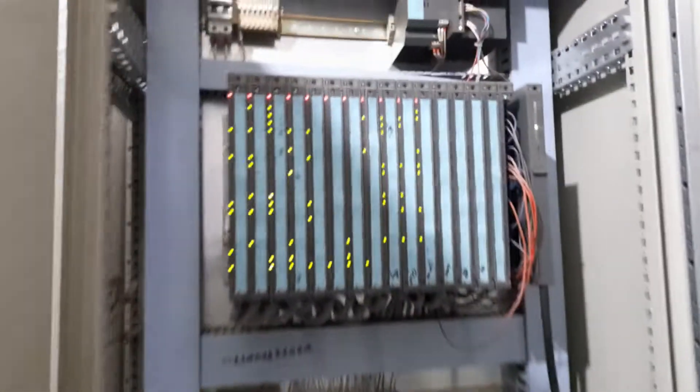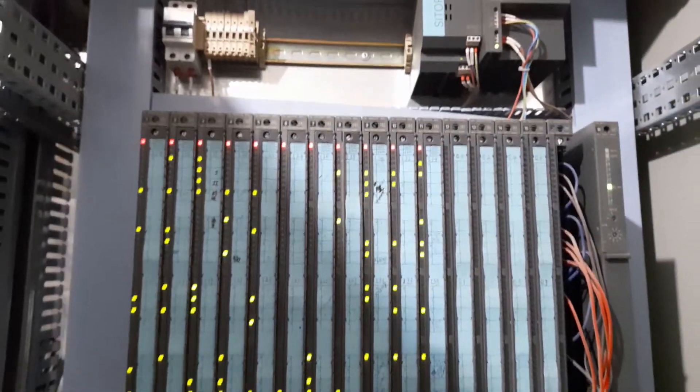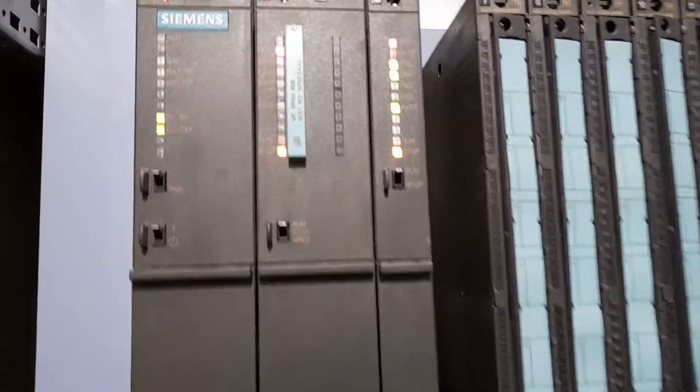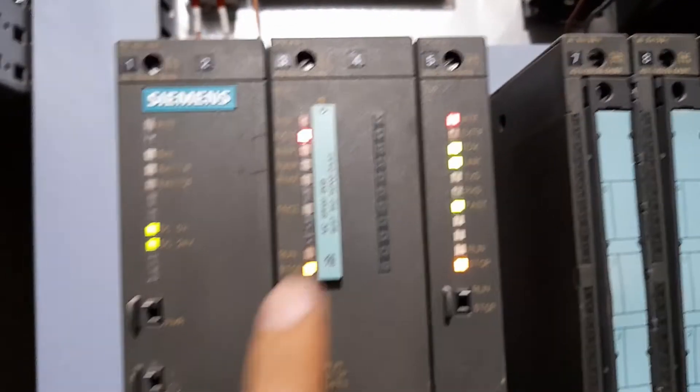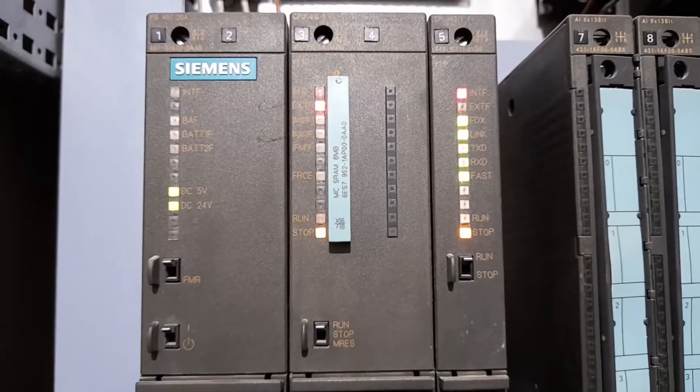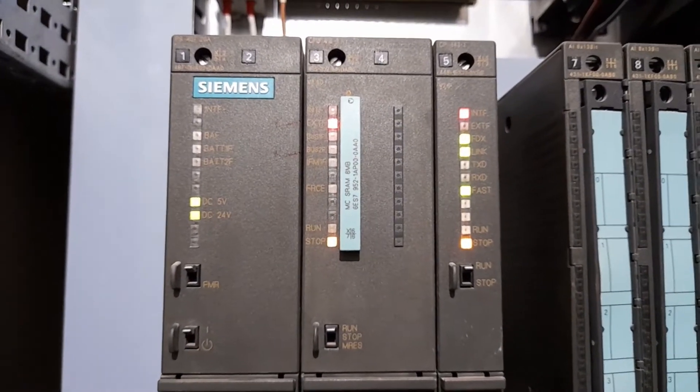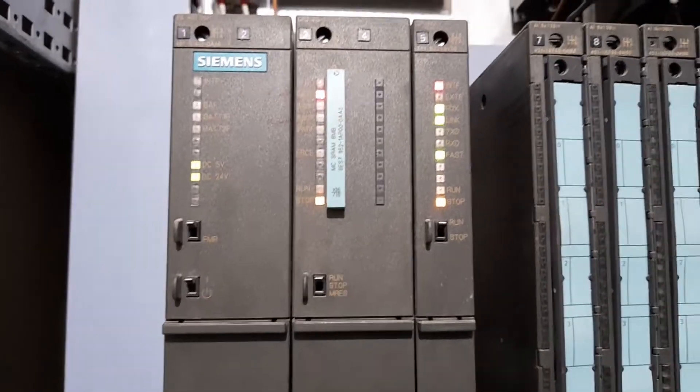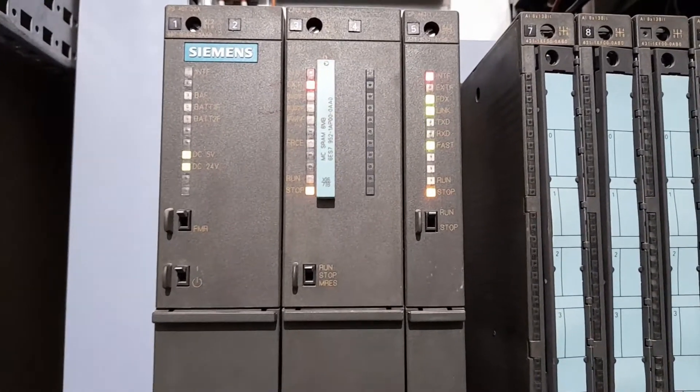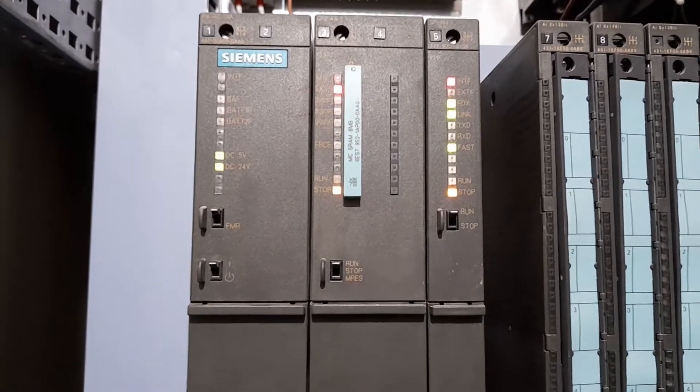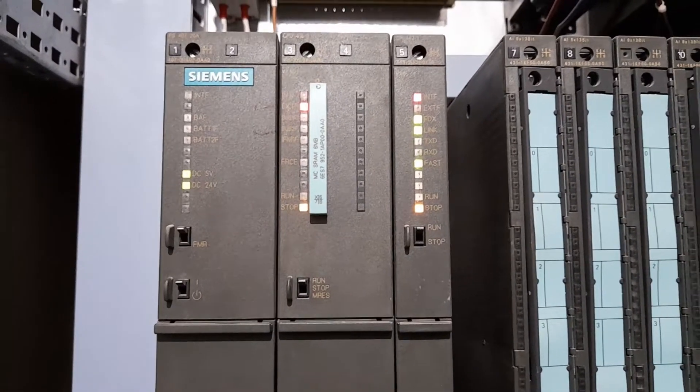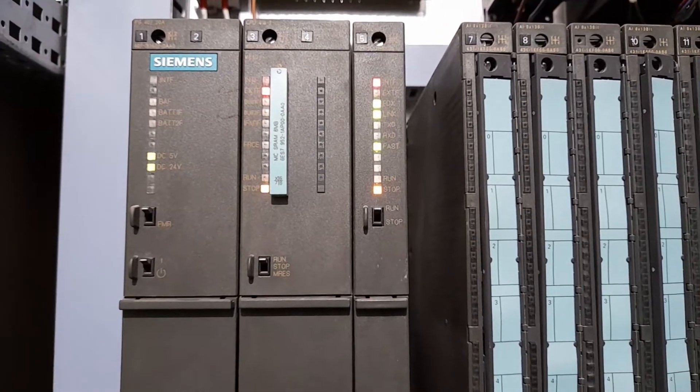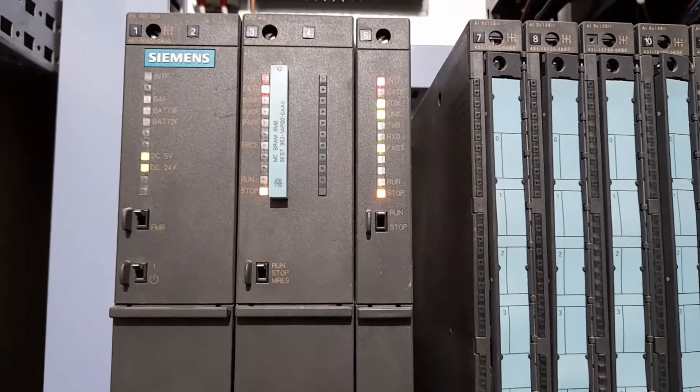These are the error LEDs and this is the third rack. So, this fault position actually means that the program in the memory of this CPU is no more running. The processor is not scanning the program and this is why it is in the stop mode and no equipment in the field can be operated in this position.